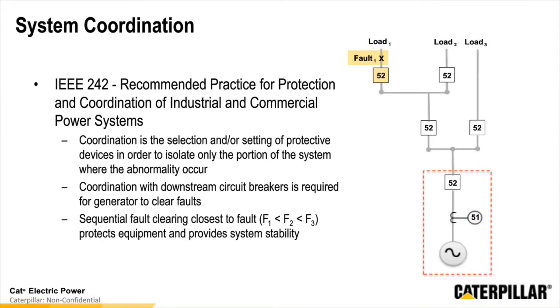And finally, it also references that sequential fault clearing closest to the fault protects equipment and provides system stability. So what this is referencing is that if we were to have a fault on load 1, like we show here, we want to clear the breaker, the 52 device, that is right in front of that fault. So there's a specific protective zone that we want the 52 device to protect. In this case, we would drop the power to load 1, but we would still be powering loads 2 and 3.